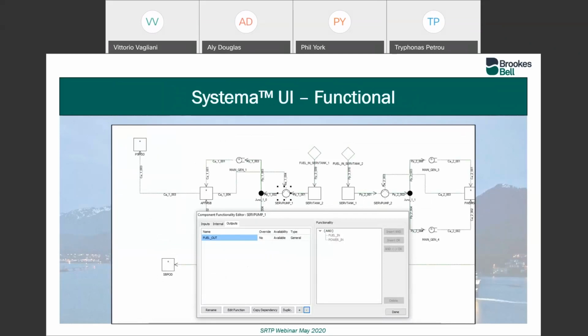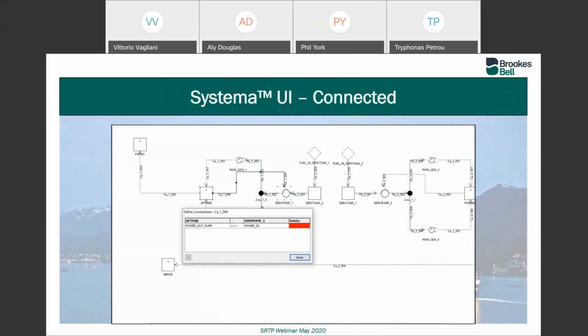The systems are functional, so by that we mean that every component actually has a series of inputs and outputs, and the outputs of a component are dependent on its inputs, which can be defined within the software using Boolean logic. The systems are connected, so by that we mean that the output of one component is connected to the input of another. So if that output was to fail, then the input of that component fails, and therefore we can have that knock-on effect of a functional loss.